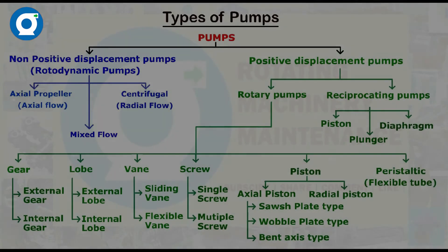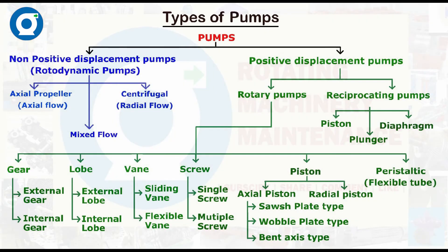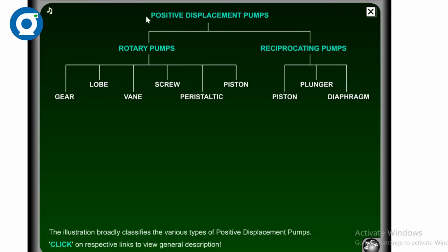Under the two major categories of positive and non-positive displacement pumps, let's look first at positive displacement pumps. Positive displacement pumps are constant flow machines. Unlike centrifugal pumps where flow capacity varies according to discharge pressure, positive displacement pumps are suitable for applications requiring small or medium pumping capacity against high pressure, and to inject or adjust very precise quantities of liquid against varying suction and discharge pressure conditions.